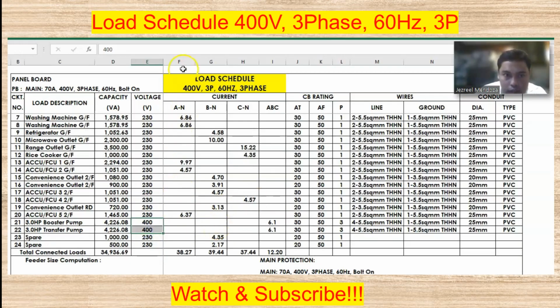And then load balancing, be sure that the 3 lines are balanced, so to avoid overheating. And then for the circuit breaker, if it is single phase line to neutral, we use 1 pole. Pag 3 phase na 400 volts, we use 3 poles.